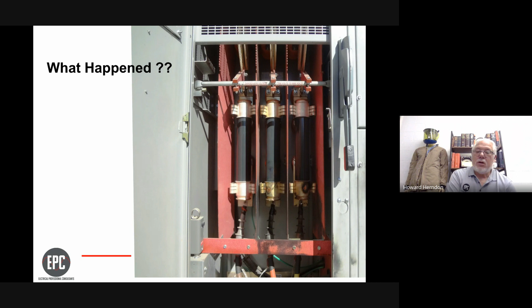In this particular case, the gentleman opened the door because there's not an interlock that you could defeat. You have to turn the switch off to open the door, and then he turned the switch back on. The cables on the bottom go out to the PV field. Once the AC power has been turned off, the inverters will de-energize because they're no longer tracking the 60 cycle sine wave. But he turned the switch back on, and as you can see on the right-hand side of that one fuse, you have a burnt spot, and on the center fuse, you have a burnt spot. The gentleman took a 1,000-volt meter and placed it on a 4,160-volt system.